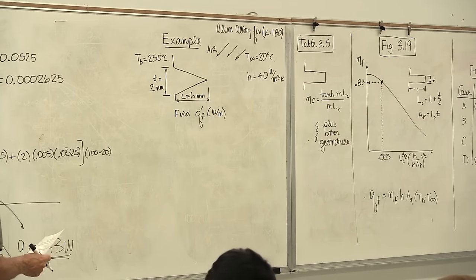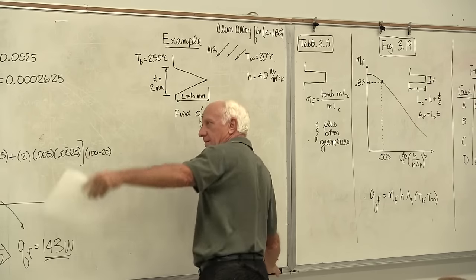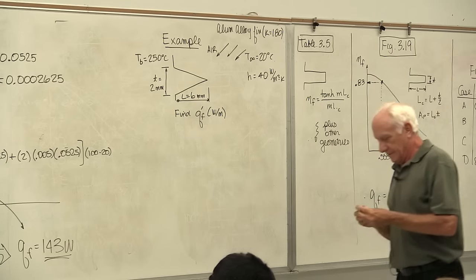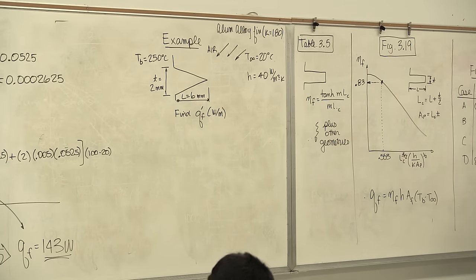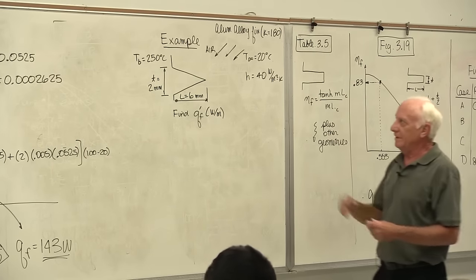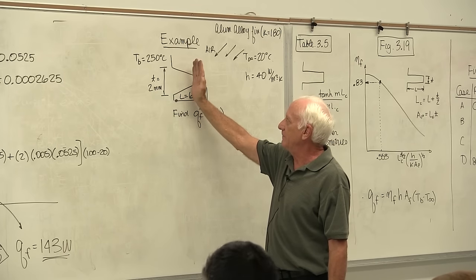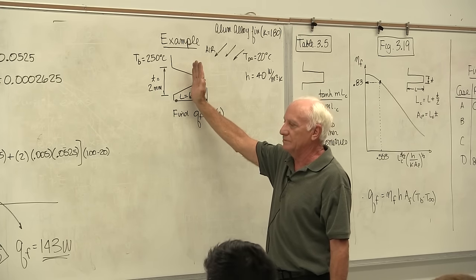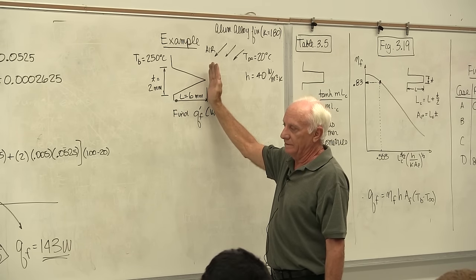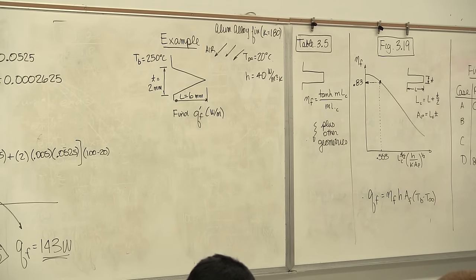Can we use Table 3-4? No — at the base the cross-section is large, at the middle it's smaller, near the tip it's nearly zero. The cross-sectional area is not uniform, so Table 3-4 does not apply. Moving on to Table 3-5 and Figure 3-19 — Figure 3-19 has a second line for the triangular fin.